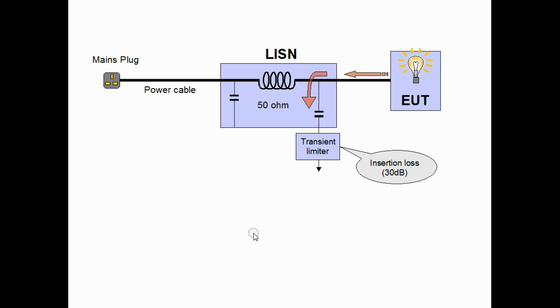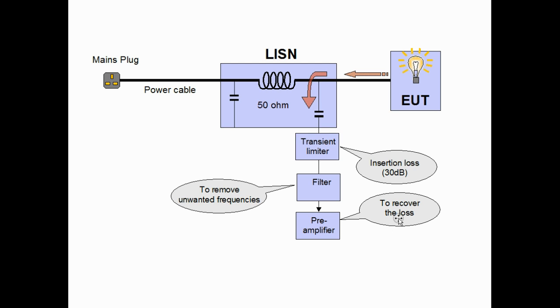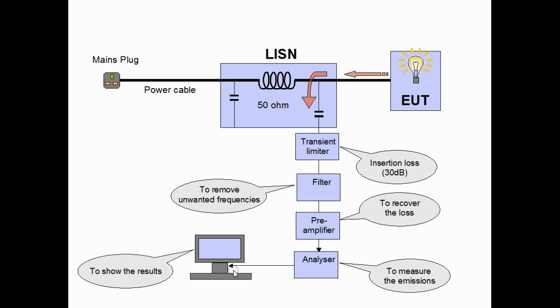To look further down our measurement network, the next stage may be a filter to remove unwanted frequencies then a preamplifier which will recover the loss caused by the transient limiter and then to our analyzer which actually makes measurements. This may be connected to the PC to show results and to control the whole system. Finally, the filter may be replaced by a device called a preselector. We'll talk about that more in a later session.